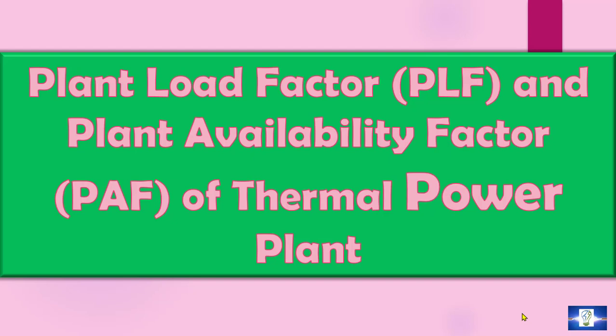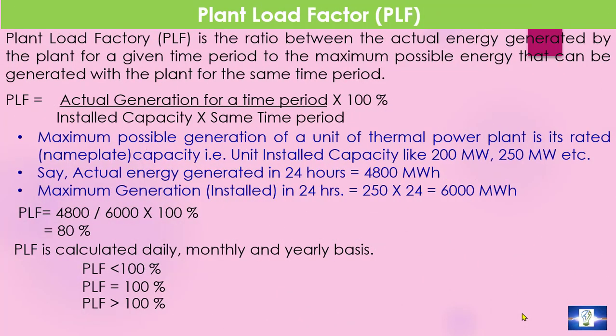I am Devashish Dewan. Today I will discuss plant load factor and plant availability factor of a thermal power plant. Plant load factor means PLF. The PLF is the ratio between the actual energy generated by the plant for a given time period to the maximum possible energy that can be generated with the plant for the same time period. It can be expressed as PLF is equal to actual generation for a time period divided by installed capacity into same time period into 100%.